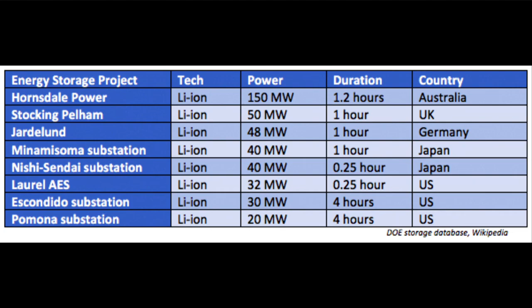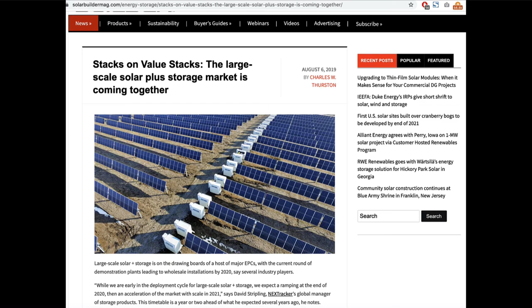So it makes a lot of sense to use these very large PV power plants as energy storage plants, because there's not a lot of room taken up by the energy storage, and you've got a ready-made interconnection that's already built for however many hundred megawatts you need. You don't have to build the substation twice, because these substations are very expensive. I think over the next 10 years, a good portion of these energy storage projects are going to be augmenting PV sites and using that same interconnection.